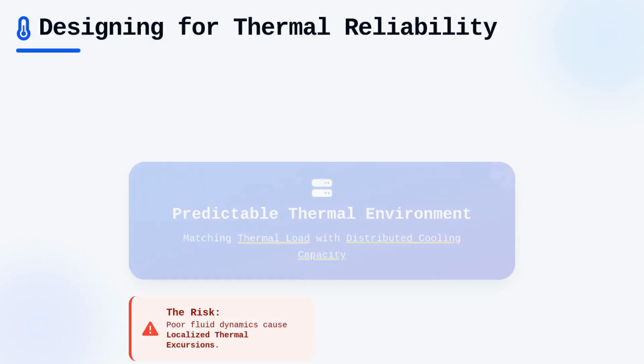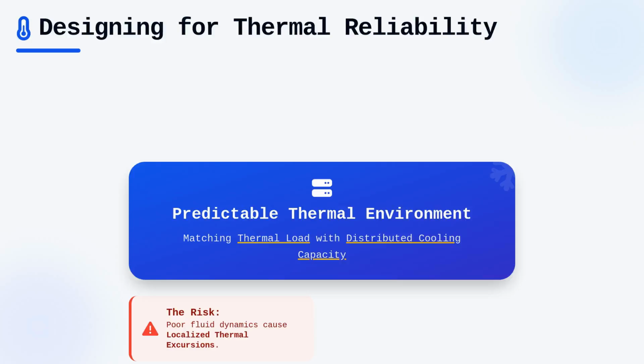Designing for thermal reliability requires a commitment to rigor that separates a functional space from a source of expensive equipment failure. Maintaining strict control over the intake temperatures at the server level is the ultimate objective of every design element we have discussed. If the airflow bypasses the intakes, or if the heat rejection units are positioned without considering the fluid dynamics of the room, you will encounter localized thermal excursion events. Our goal is to create a predictable environment where the thermal load is matched by a corresponding, well-distributed cooling capacity that respects the architectural constraints of the facility.